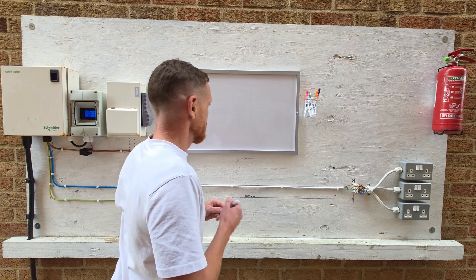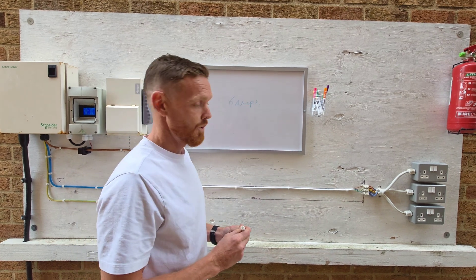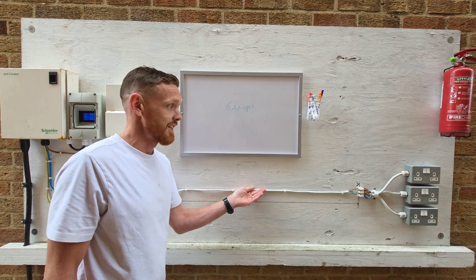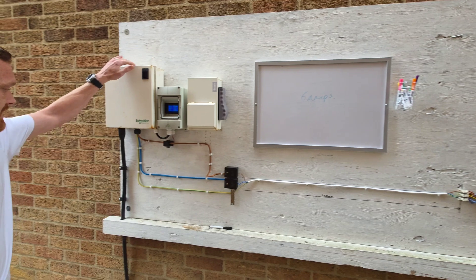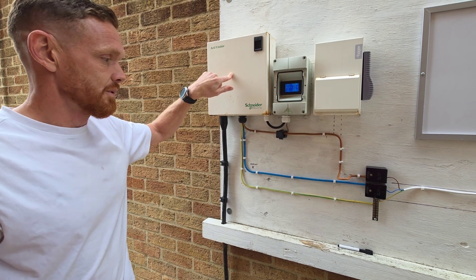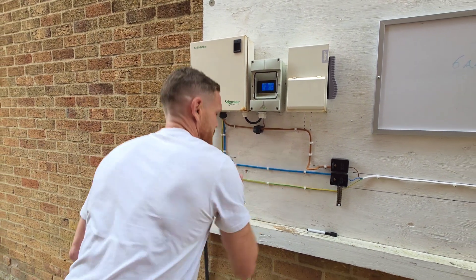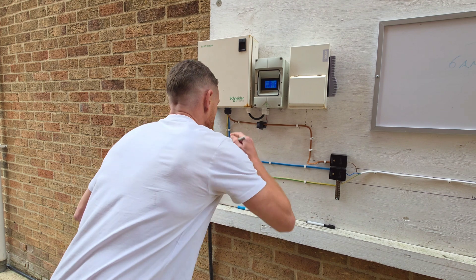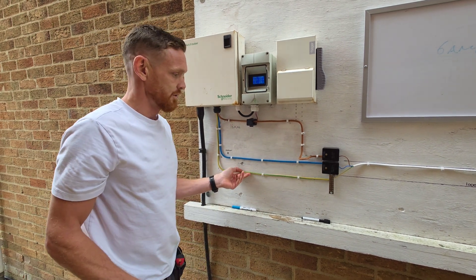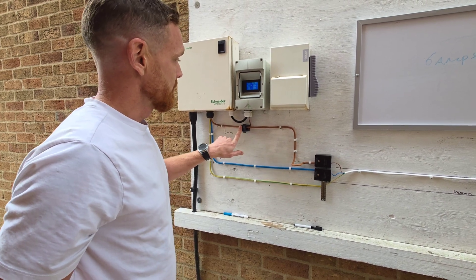This small cable is a 0.75mm flex and it can safely take six amps — that's what we're told as electricians. Now what we've got here is quite a dangerous setup, it's more of a destruction rig than a safe electrical rig. We've got a 16mm cable coming in that goes to a breaker, a main switch inside this box, then out of there we have a 50-amp breaker feeding these 16mm cables.